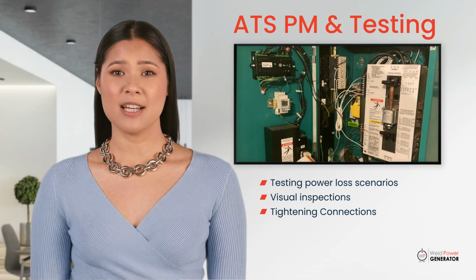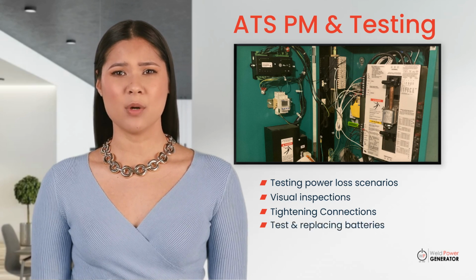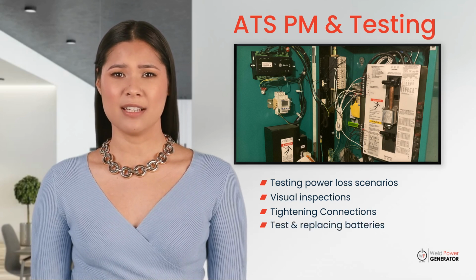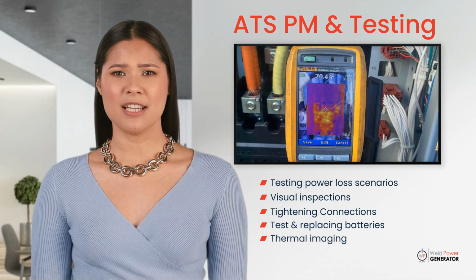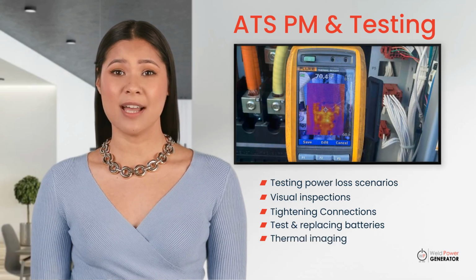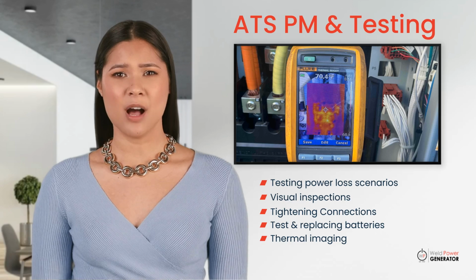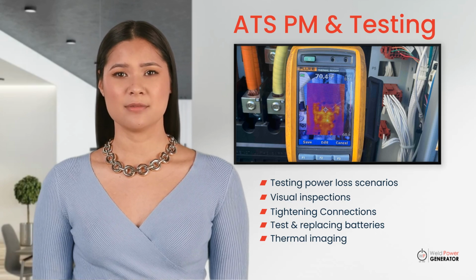For ATS units that rely on batteries for backup, it's important to regularly test and replace the batteries before they reach the end of their service life. Using thermal imaging can also be a valuable tool for identifying hotspots or areas of excessive heat buildup, which can indicate potential problems before they lead to failures.